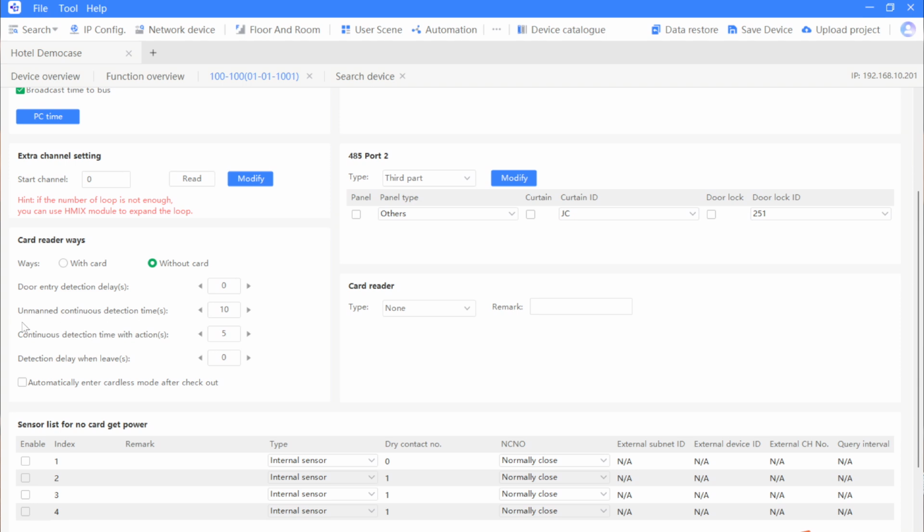For example, if the guest leaves the room and something like a fan or a bird triggers the sensor, this is just mistriggering, so the sensor will not keep the detection status for 5 seconds, maybe 2 or 3 seconds, and then it will judge there is no one, so it's mistriggering. So you must set the time to avoid mistriggering.